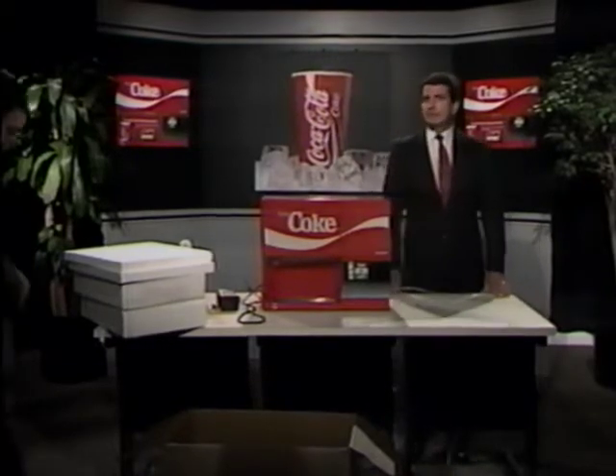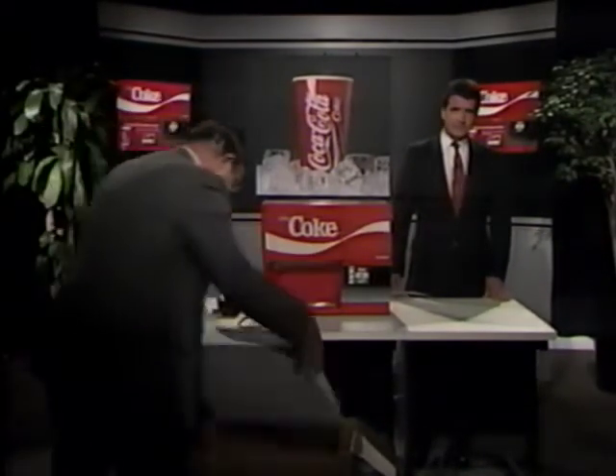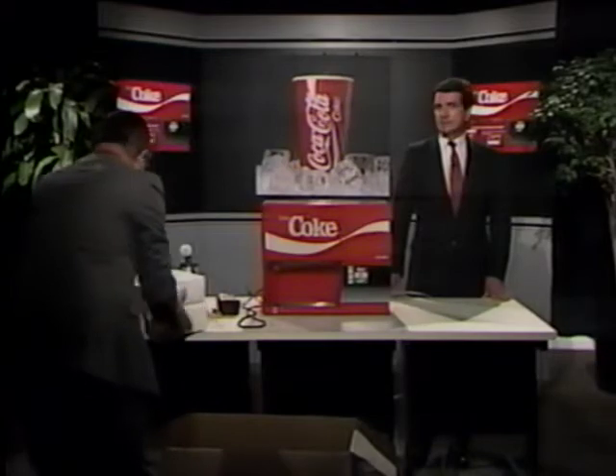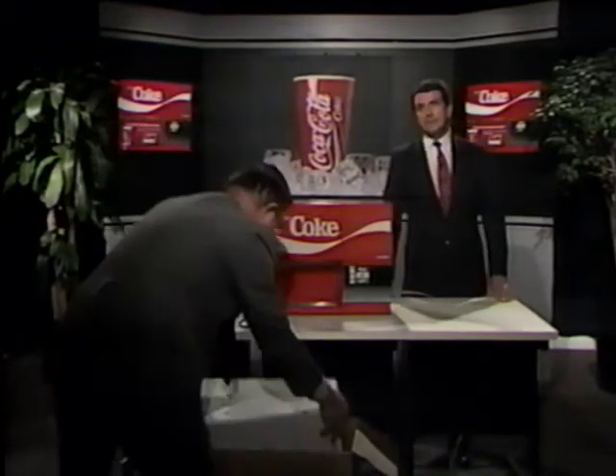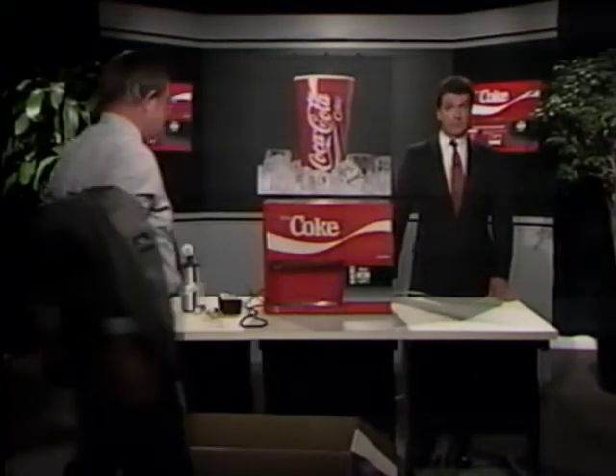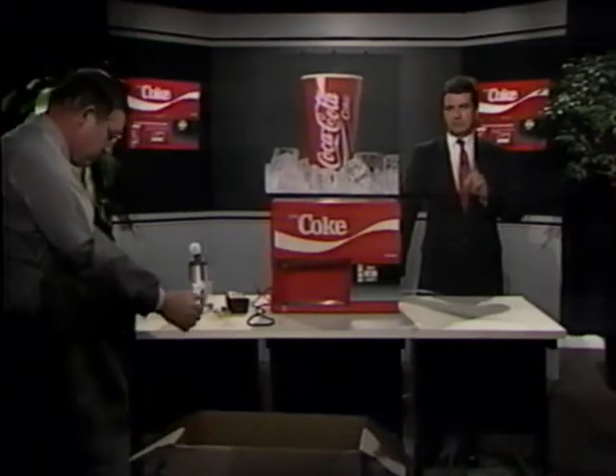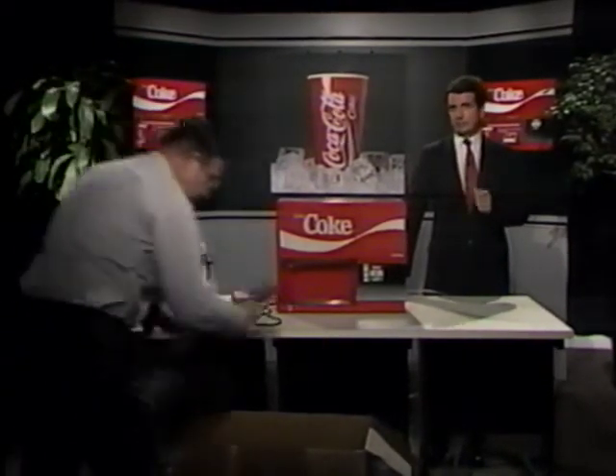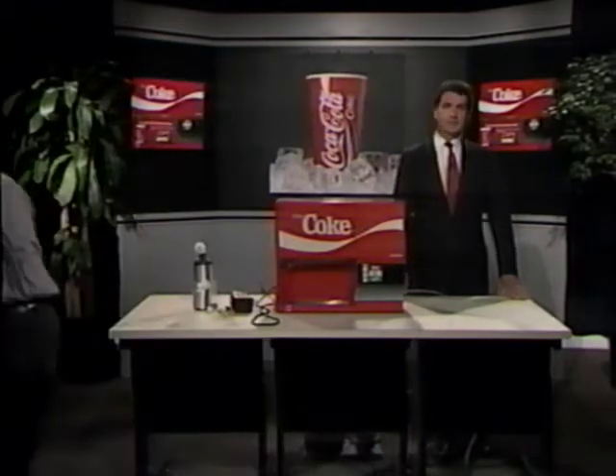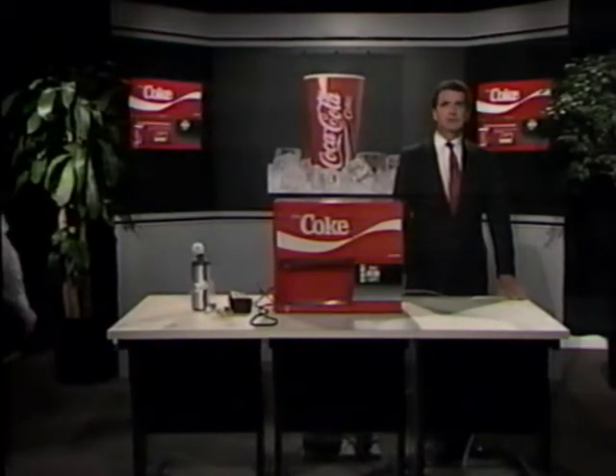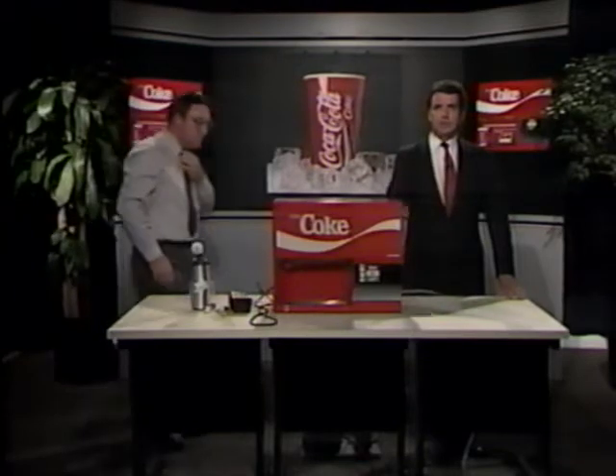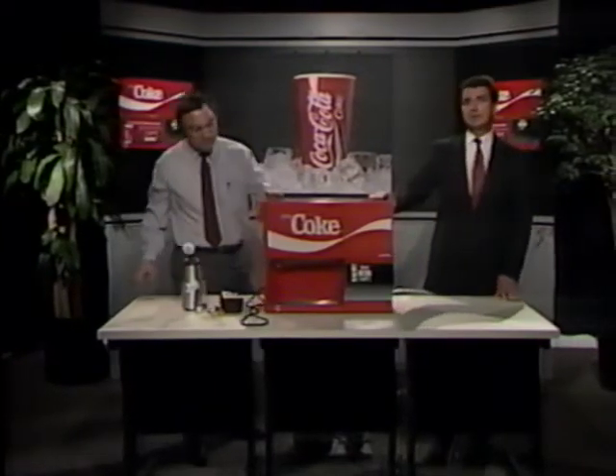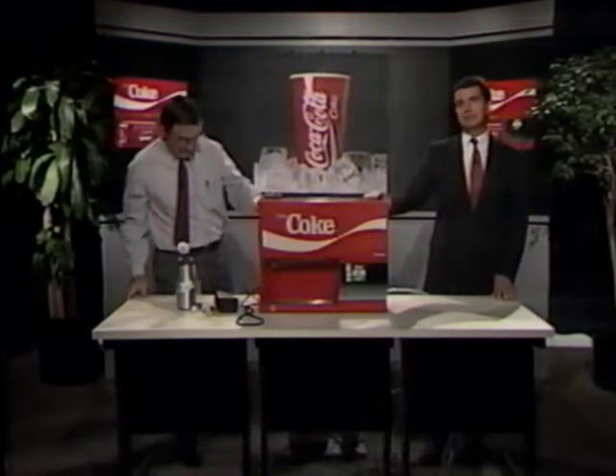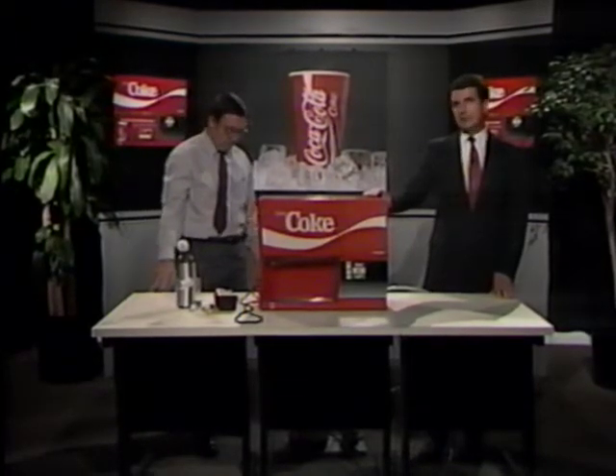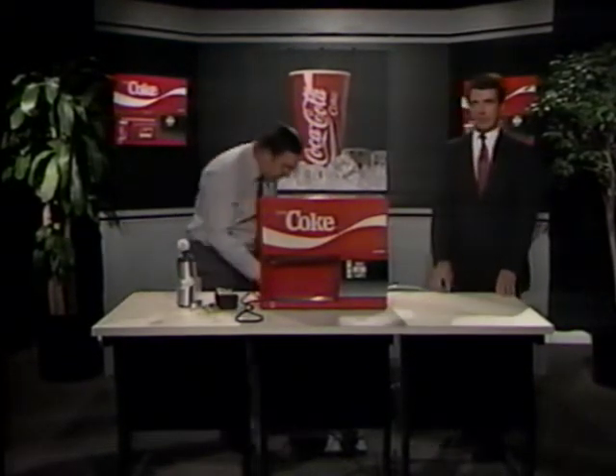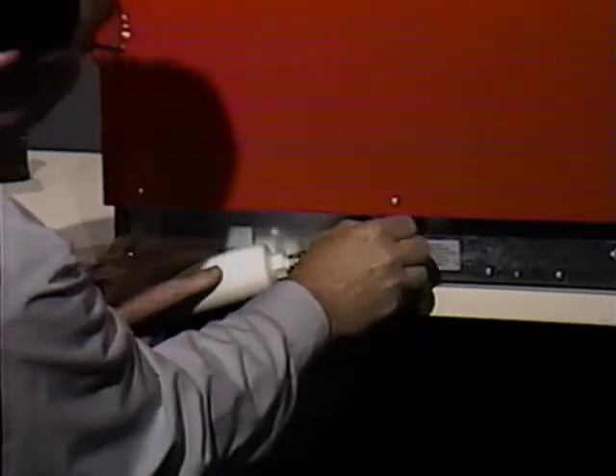So what do you have to have in your shop for preparing the BreakMate for installation? It's not complicated, not expensive. You need electrical outlets and a filtered water hookup for one or more machines. And you should remember to thoroughly flush your water filter when it's first installed in your bench testing setup. Proper bench testing includes the following steps. You remove the machine from the packing carton and check for visual damage. If everything's okay, the next step is to connect the filtered water line to the inlet valve on the back of the machine.